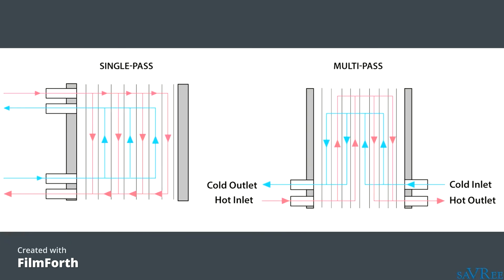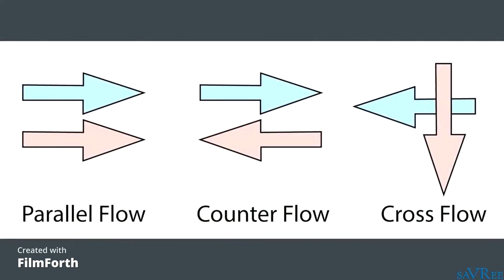Flow through a plate heat exchanger may be parallel, cross, or counter. Plate heat exchangers usually use counter flow, as this is the most efficient type of flow for heat transfer. Counter flow is also sometimes known as contra flow.